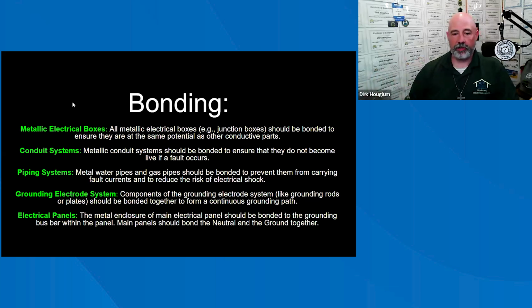Creating one giant loop, basically. Grounding electrode systems: components of the grounding electrode system, like grounding rods or plates, should be bonded together to form a continuous grounding path, just like everything else. Electrical panels: the metal enclosures of the main electrical panels should be bonded to the ground bus bar within the panel. Now, when you're looking at sub panels, they should be separated.